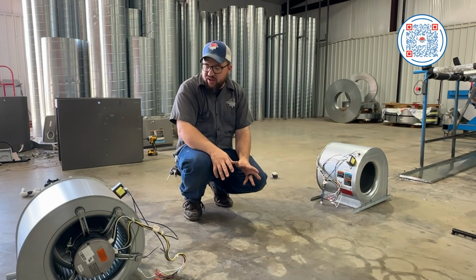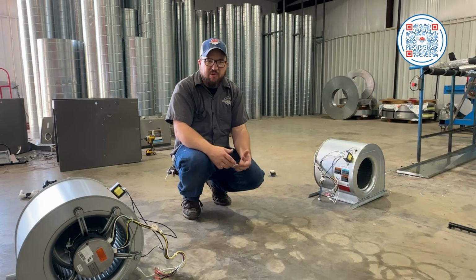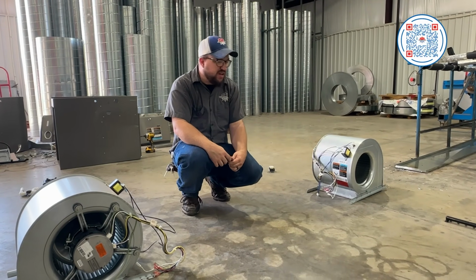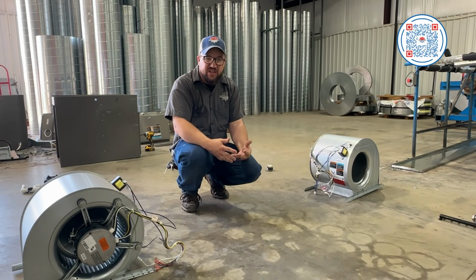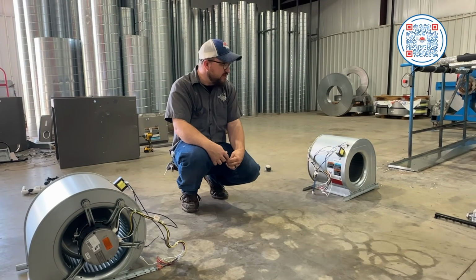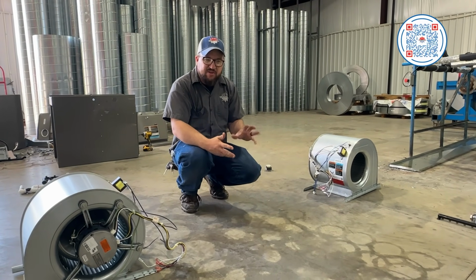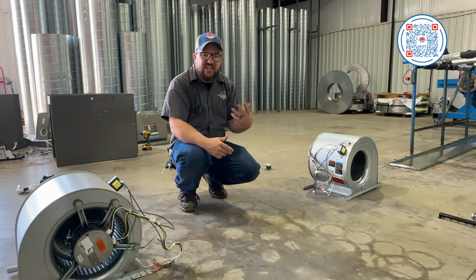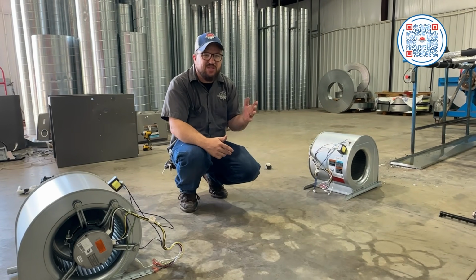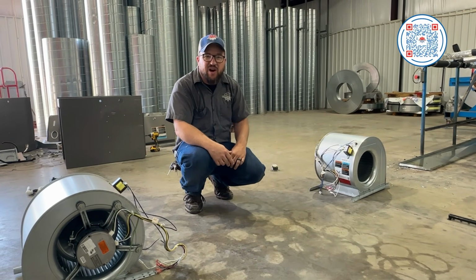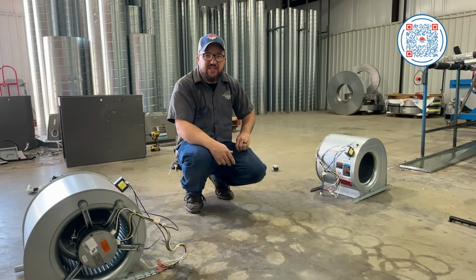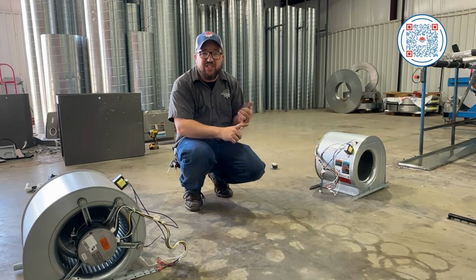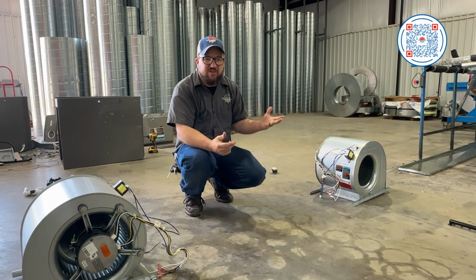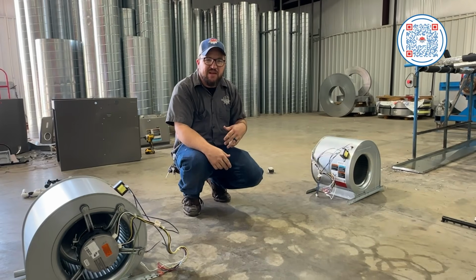On the wheel, we do see them fall apart, and that's never fun when they do. They kind of give you warning signs sometimes, which I always call a slinky sound. If you're starting to hear any kind of noise like that, definitely give us a call, have us check out your unit, especially if you haven't had it maintained in a while. We'd be happy to come out and do a maintenance. Make sure your blower wheel's clean, because that's another factor; a lot of dirt built up on that can mess up the balance of that motor.